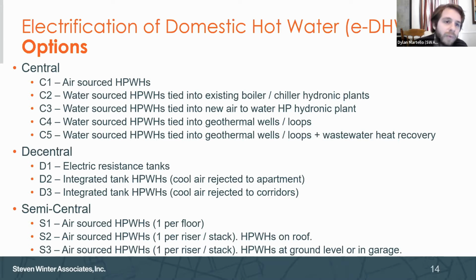But this dovetails nicely from the existing building scenario, where, when you have an existing boiler plant and chiller plant that needs to get upgraded for space heating, you can upgrade that to an air to water heat pump hydronic plant. So you'll have a rooftop unit that will utilize the outdoor ambient environment to produce hot water for a hydronic loop that's providing not only space heating to the building, but now also domestic hot water. And when you do that, you can have what we call a low temp hydronic loop. If you have heat pumps in the actual apartments utilizing the water from this hydronic loop, you can maintain a fairly mild temperature, somewhere between 70 and 100 degrees Fahrenheit, or 70 and 90 degrees Fahrenheit, roughly, in that hydronic loop that's just running around the building.